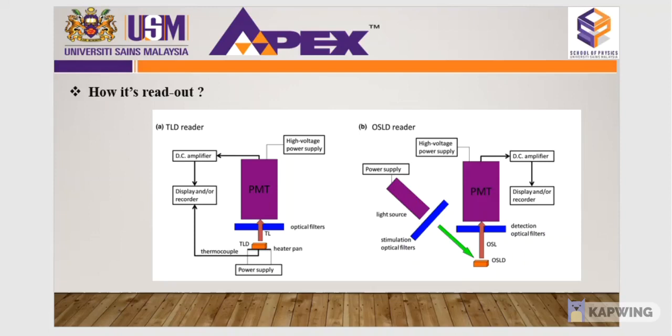The number of electrons produced by the photomultiplier tube is magnified more and more until they reach the anode, produced by striking electrons under applied high voltage. These striking electrons are recorded as a count. The number of counts on a reader depends on how many light photons reach the photomultiplier tube, which in turn depends on how much dose is on the TLD. More dose means more electrons in the band gap.